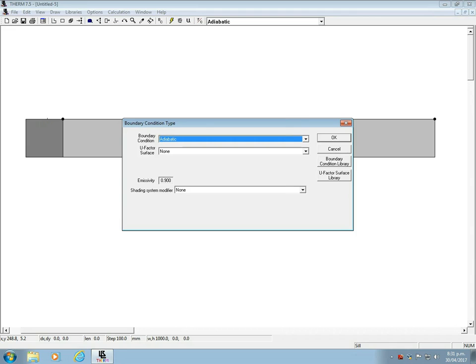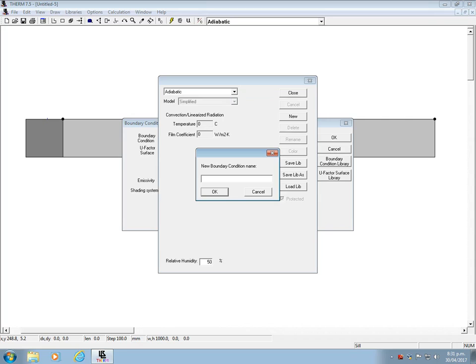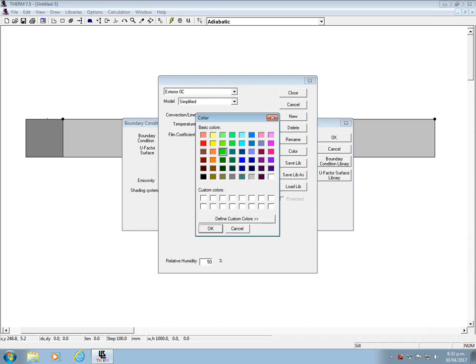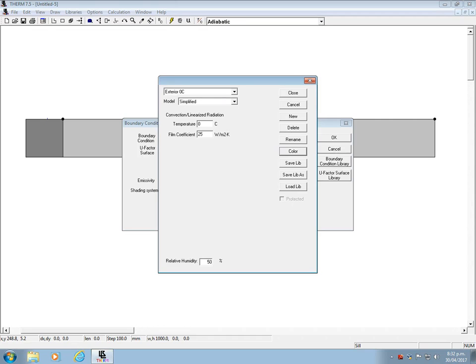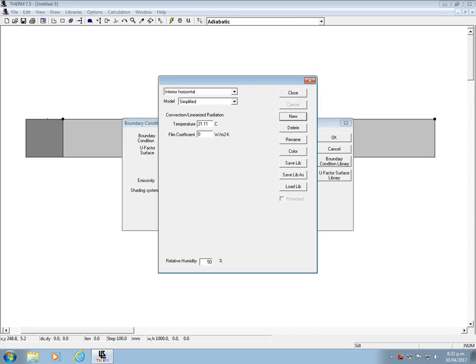Let's set an exterior boundary condition. And let's say it's 0 degrees on the outside. And we also need to add a film coefficient, which is the inverse of the surface resistance. So in our case that's 25. And for the interior conditions we are choosing to go with 20 degrees Celsius for the indoor air. And the inverse of the surface resistance here is 7.692. And you can also assign some colors for your boundaries to remember which is which.